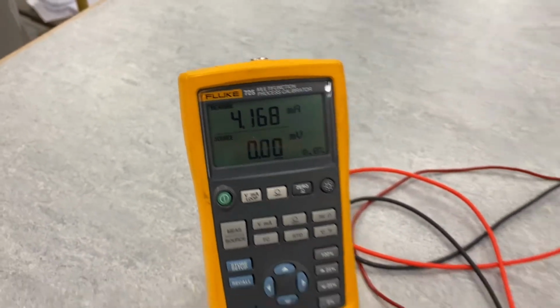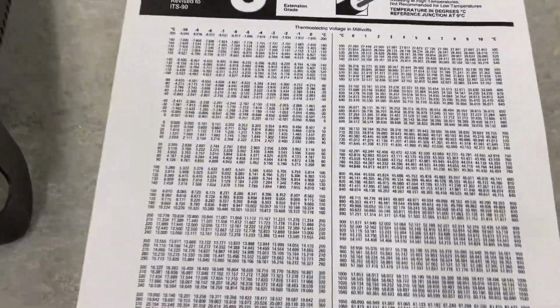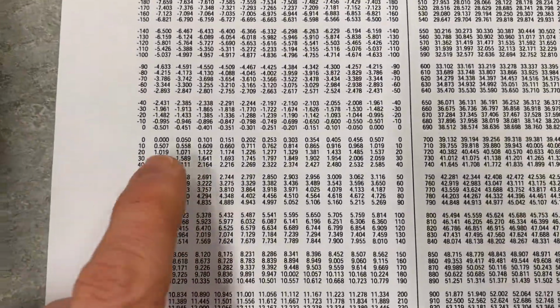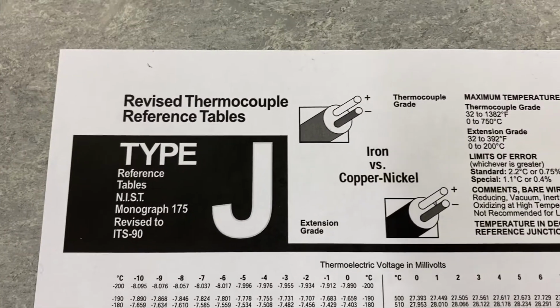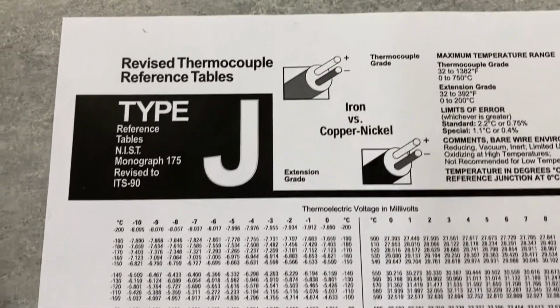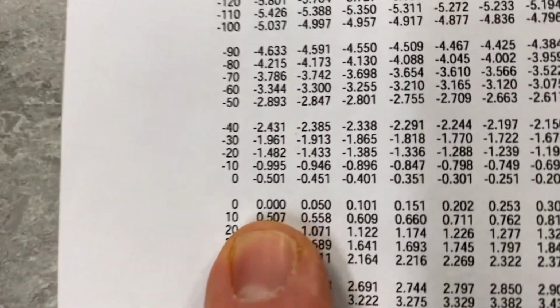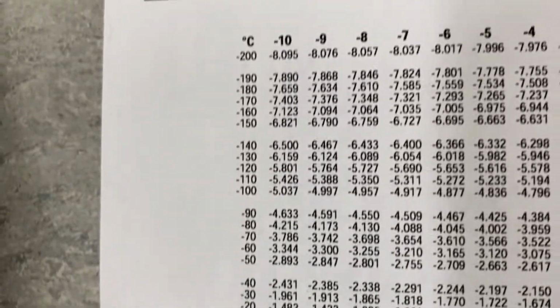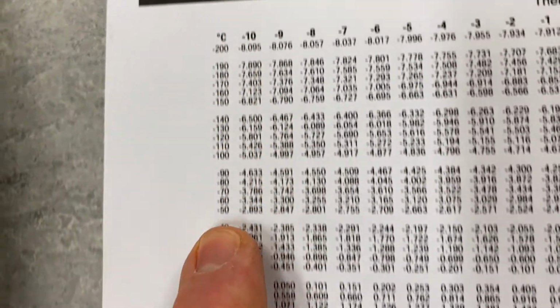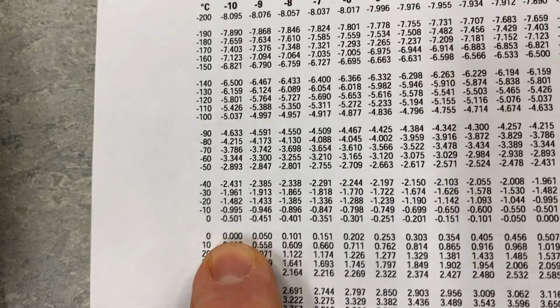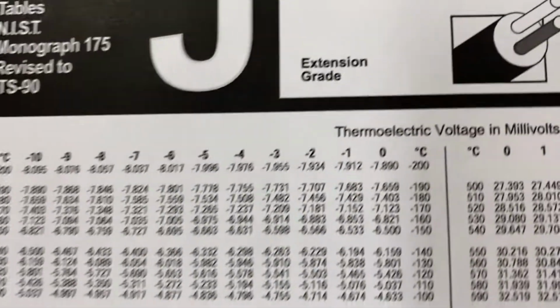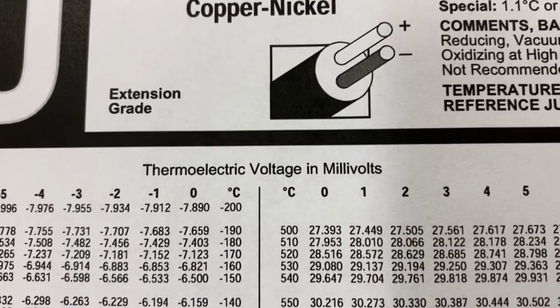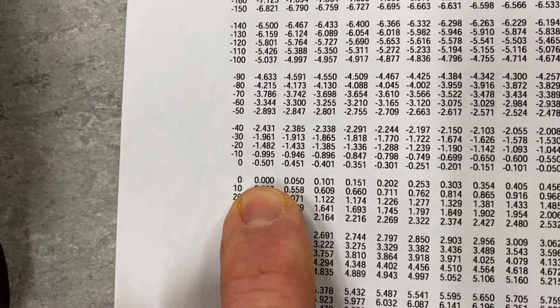So we're going to be calibrating this for a 0 to 100 degree input. We need the thermocouple table over here. You can see, looking at the thermocouple table, this is for the type J thermocouple that we're dealing with here. The value for 0 degrees C, following the table down, is 0 millivolts. So you can see the table over here is in thermoelectric voltage in millivolts. So 0, and that's what we're doing right now for our 0.